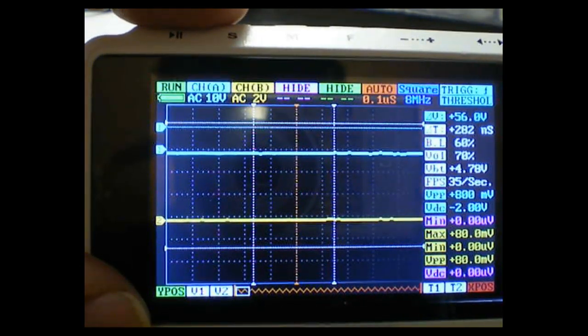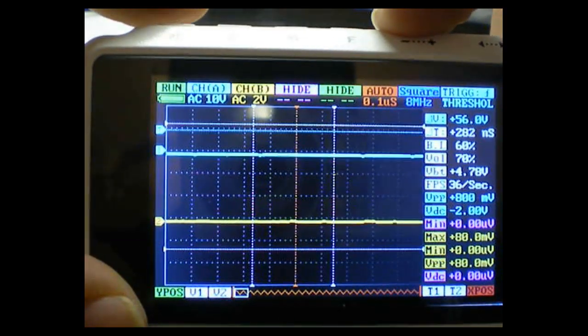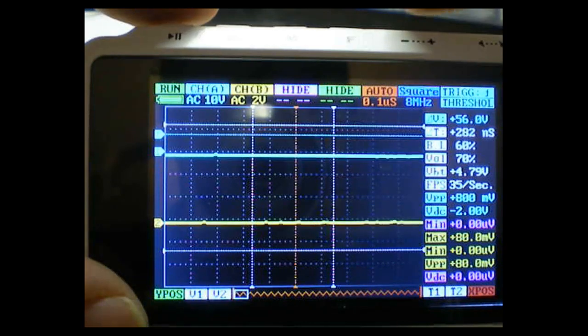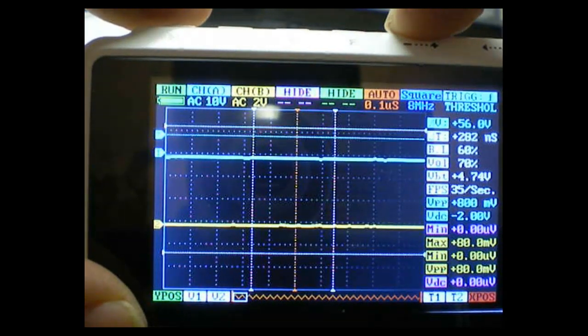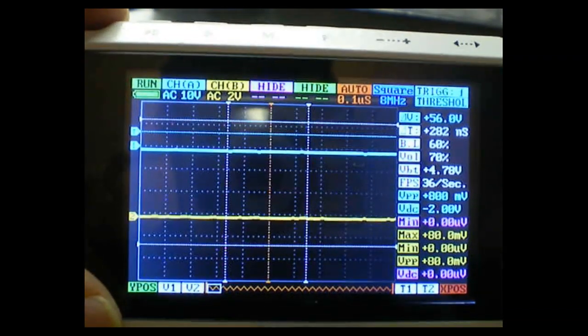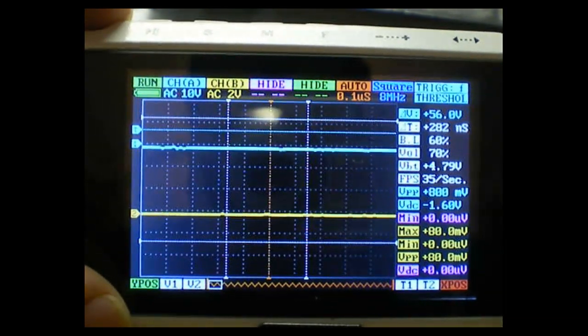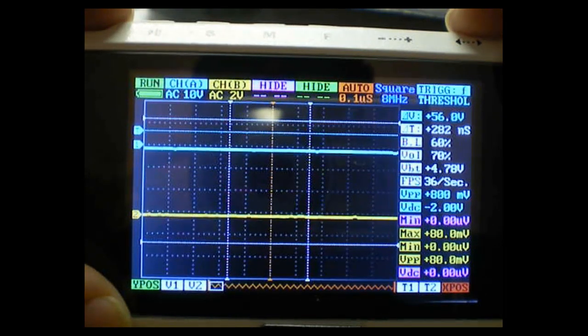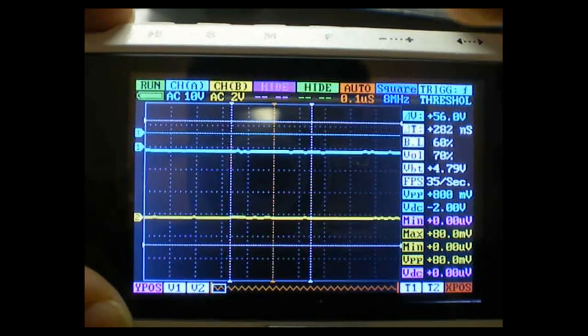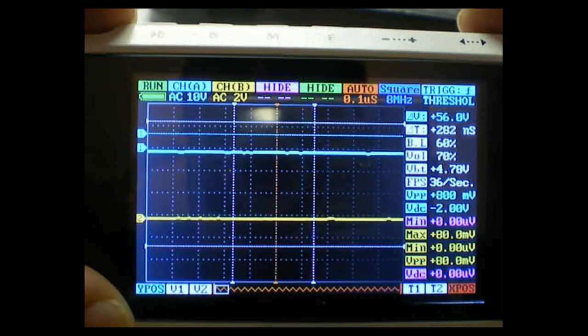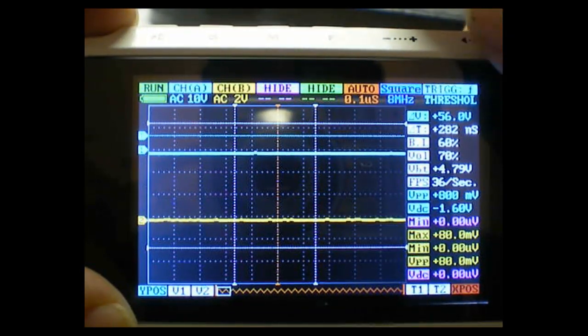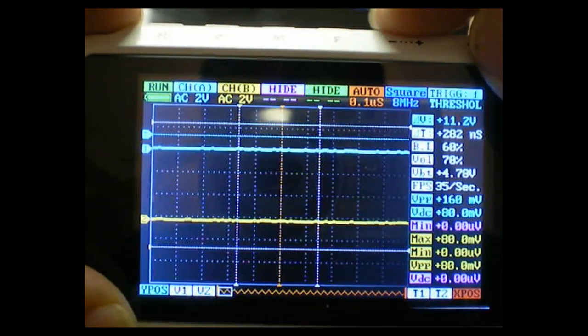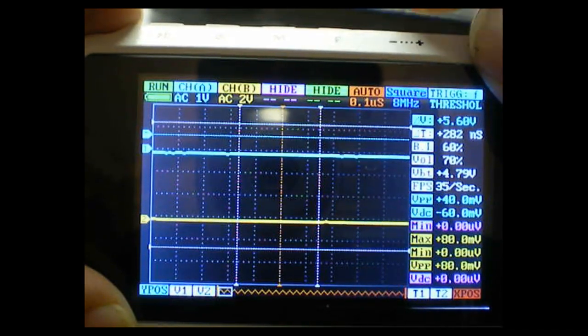Which is the threshold level. And now the plus or minus jog will set there and you can see the trigger level line right here is moving with the plus or minus jog key. Same holds true for any of these other menu items. Let's go back and look at channel A for a second. I'm going to channel A right now. I'm selected on volts per division. If I use the plus or minus jog key, I can step through the various scales, volts per division.